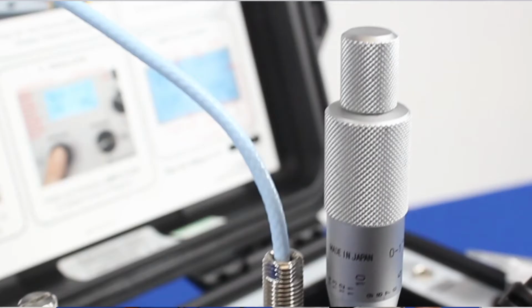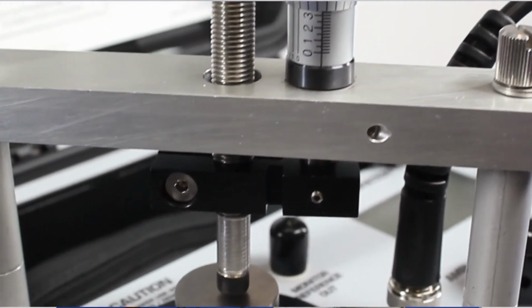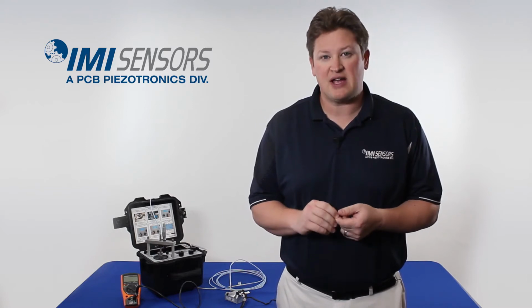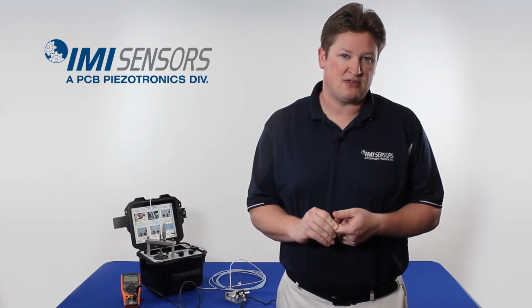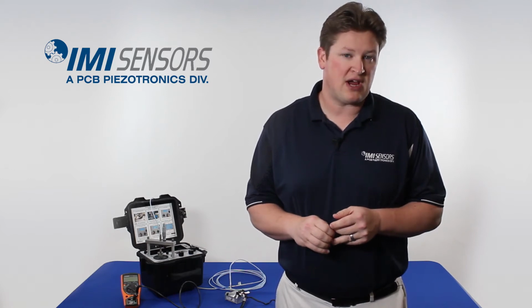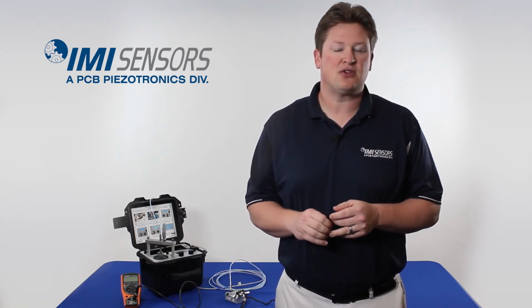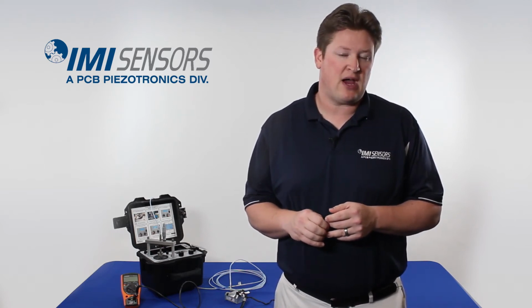And it's an excellent calibration method. If there's something wrong with the probe system, which is the probe, extension cable, and proximeter, the technician will find out using that method. The second method is dynamic, where you actually simulate real machinery vibration conditions to create a calibration certificate. And this is a lesser known method, but its advantage is while you're doing so, you can also system check, or loop check, the vibration monitoring system, which is a major requirement of the API 670 standard.